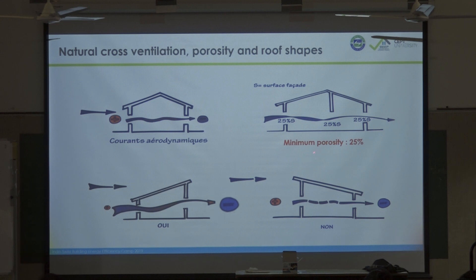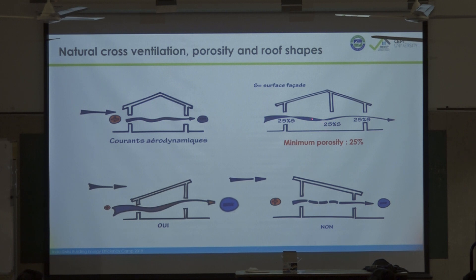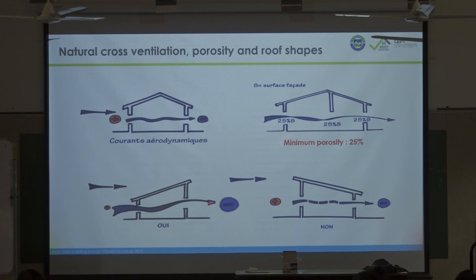The porosity — which I define as the percentage of openings in each facade — must be sufficient. The minimum percentage in Reunion is 25 percent; for tropical climates I think a minimum of 30 percent would be better, on both sides and inside the building to minimize friction. Always combine the difference of pressure with a porosity of 25 percent on each facade.